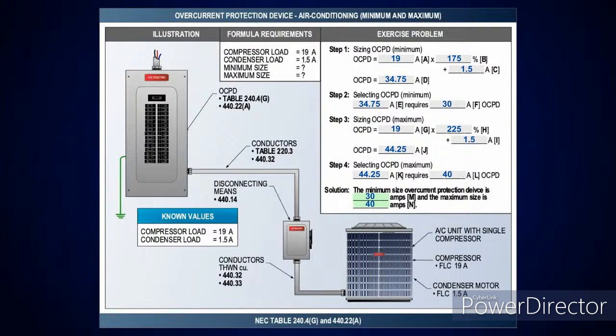Right. Now, if I'm going to size the maximum, it'll be in 440.22A, but if somebody's looking at their 2023, you're going to go down and look at exception 2 for the maximum. So say I was even doing the maximum here, I could just go up to 35 per exception 1 in the 2023 cycle. But right, I'm going to go up to a maximum. So I'm going to take 19 amps at 225% and then add the 1.5, which gives me 44.25 amps. Once again, it says I can't exceed the calculated value here, so I'm going to drop down to the next standard size, which is a 40 amp. So right, my minimum's a 30 and my max is a 40.